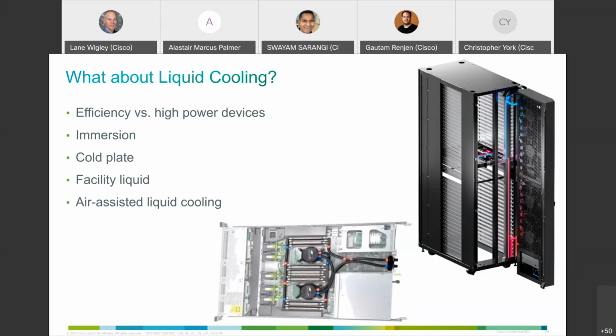One is to actually have facility liquid, meaning the facility provides you with cold water. You exchange heat from the rack into that cold water, so you don't need a lot of fans in the rack itself. That can be very efficient, but it requires a big investment, and you need to make sure that all, or at least the majority, of your equipment can run that way.